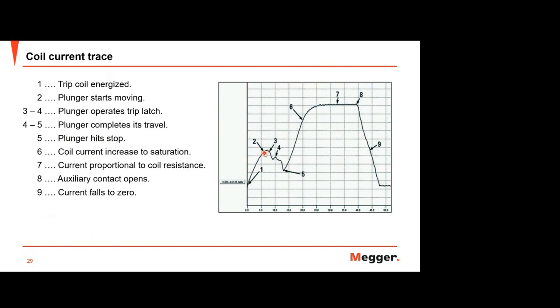Then the movement of the iron core through the trip coil generates an electromagnetic force in the coil that in turn has an effect on the current flowing through it. So the rate of rise of current depends on the change in inductance of the coil. And if you see number 3 to number 4, this is the armature operating the trip latch, which in turn collapses the trip mechanism.